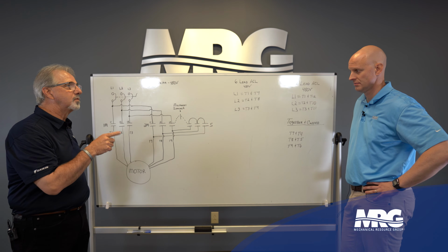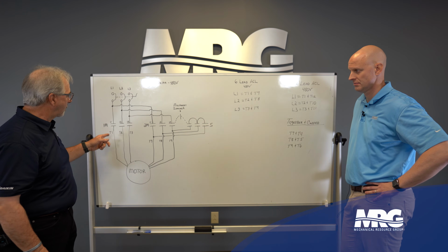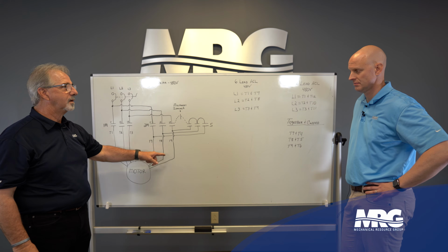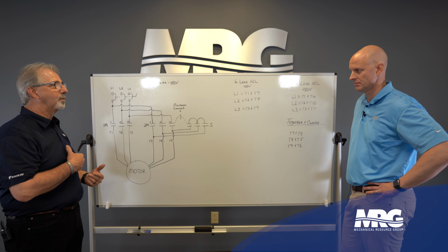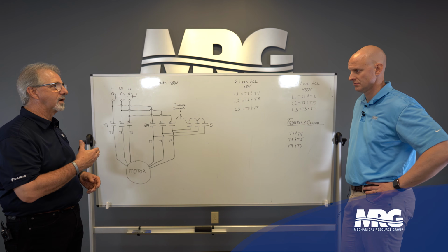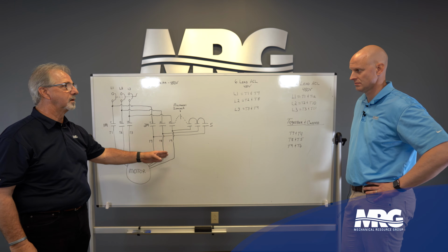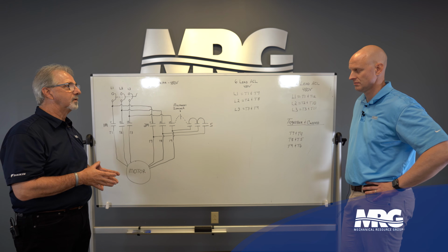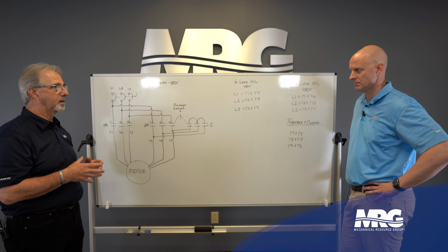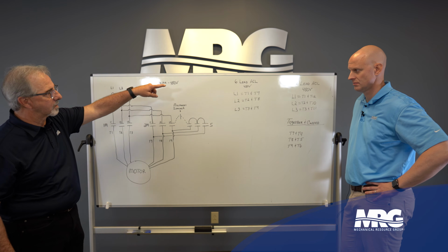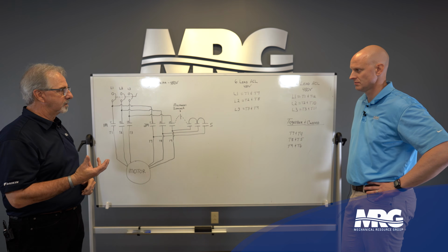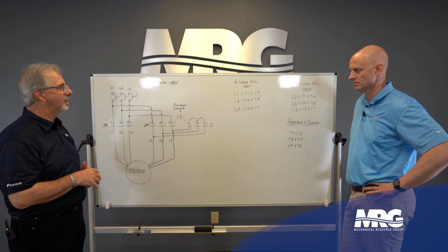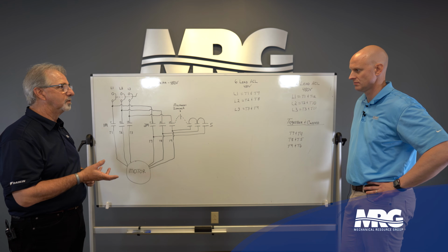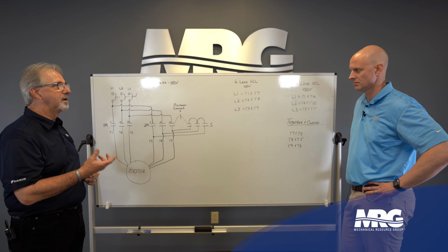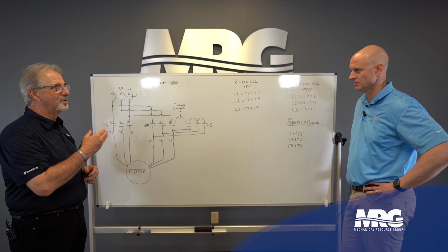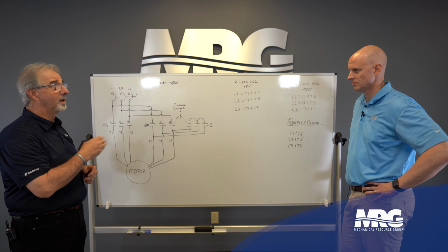Now, if you'll notice, my leads are a little bit different on this one. I go 1, 2, and 3, 7, 8, and 9. Your first question is on part winding start, why did we have to go 6, 4, 5 out of sequence? And on this one, we can do 7, 8, and 9. The motor is connected differently internally. That's why we do 7, 8, 9. And if you'll notice on my 6 lead across the line, line 1 is T1 and 7, line 2 is T2 and 8, line 3 is T3 and 9. Whereas before it was 1 and 6, 2 and 4, 3 and 5. This is 1 and 7, 2 and 8, 3 and 9.